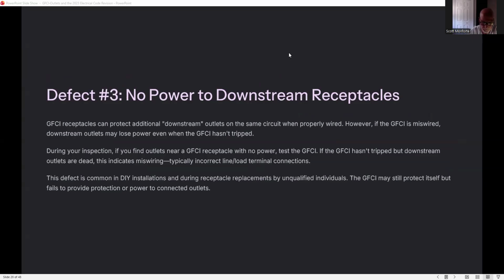Defect 3, no power to downstream receptacles. GFCI receptacles can protect additional downstream outlets on the same circuit when properly wired. However, if the GFCI is miswired downstream, outlets may lose power even when the GFCI hasn't tripped. During your inspection, if you find outlets near a GFCI receptacle with no power, test the GFCI. If the GFCI hasn't tripped, but downstream outlets are dead, this indicates miswiring, typically incorrect line/load terminal connections. This defect is common in DIY installations and during receptacle replacements by unqualified individuals. The GFCI might still protect itself, but fails to provide protection to connected outlets.